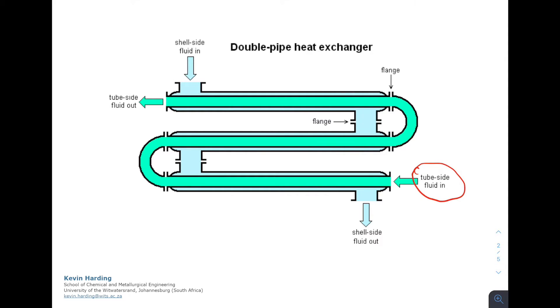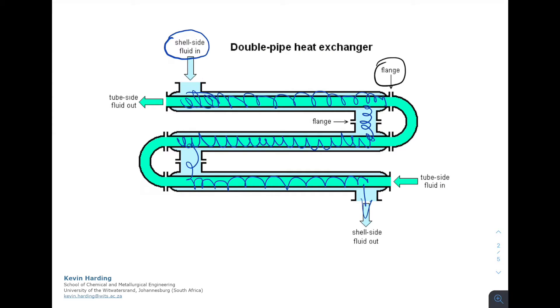The cold fluid enters on the shell side at the top — what we previously called the jacket — and flows down the length of the exchanger, cutting across and back along again, then exits at the bottom right. At the flanges on the top left and bottom right we can remove those pipe sections for cleaning. This is the more optimized double pipe heat exchanger system.